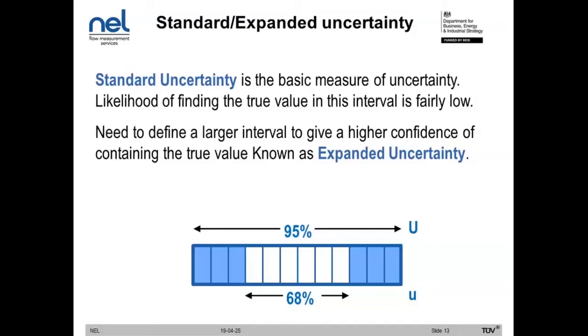So it might be desirable, and in many cases it is, to increase the confidence level, and we do this by increasing the window of uncertainty, or the interval of uncertainty. When we have a higher confidence level than the standard uncertainty, this is referred to as the expanded uncertainty. Commonly you see the value of 95% for the expanded uncertainty. Again, we'll cover where this comes from later on in the presentation.